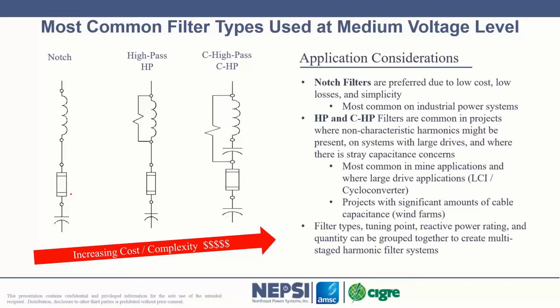And we have seen failure in capacitor banks because of being put next to a harmonic filter. So yes, very important to consider that. So the most common types of filters are notch, high pass, and C high pass, and as indicated here, the cost goes up as you go up with that type of filter.